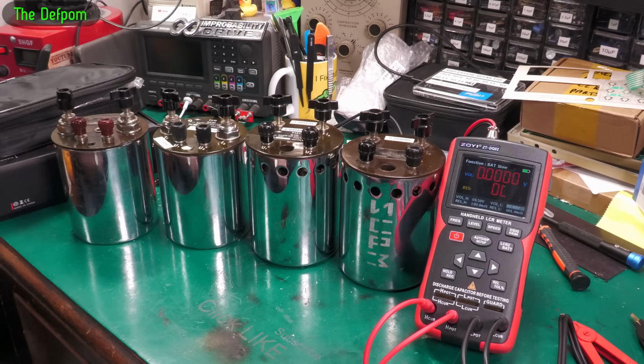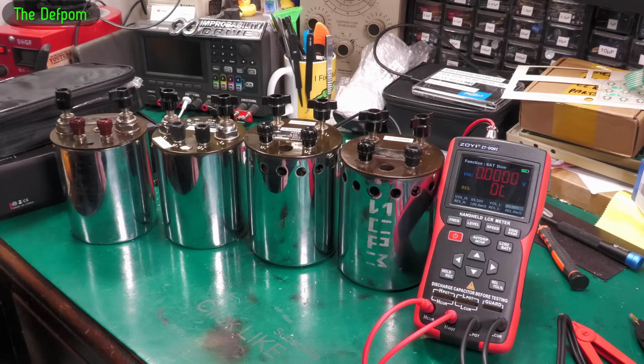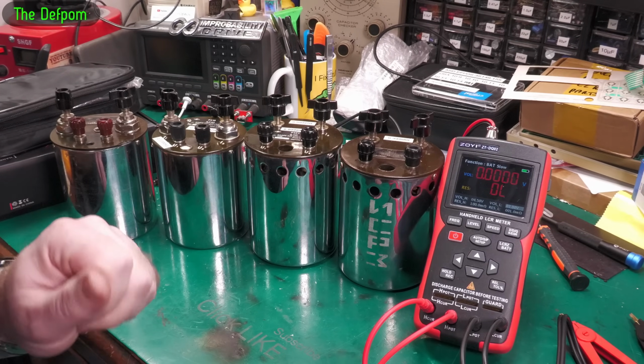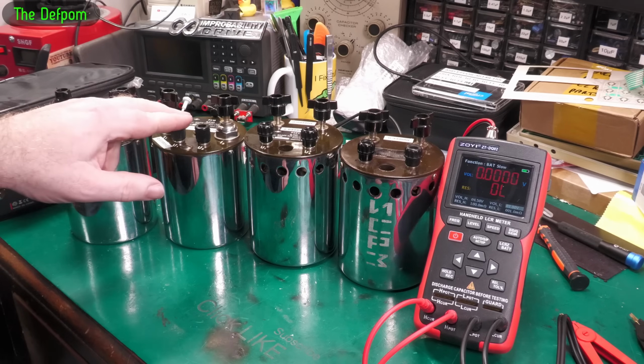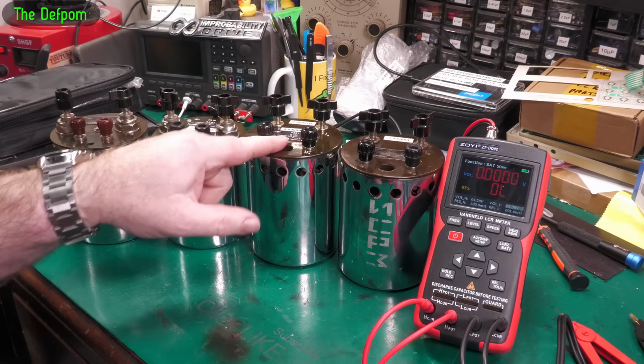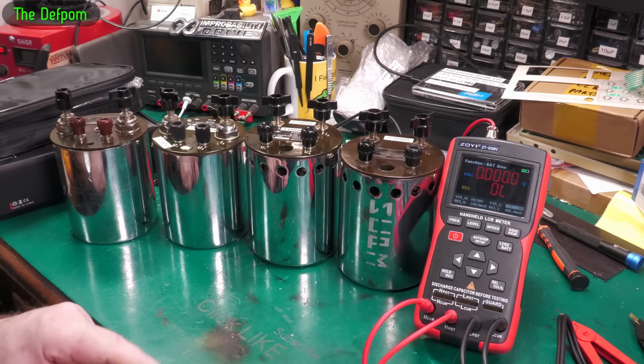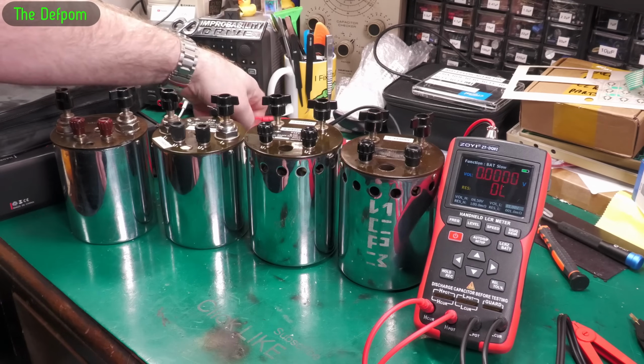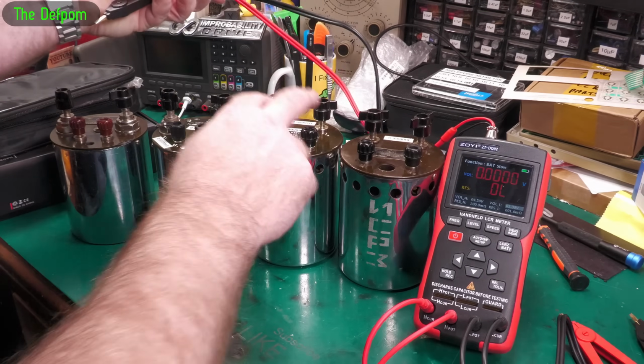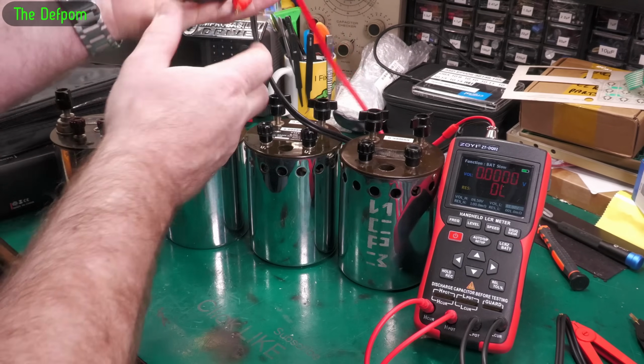So here's the first batch of resistors. I've got loads of these things, a range of values: 1 milliohm, 10 milliohms, 100 milliohms, and 1 ohm right here. I've got the terminals prepared. If you're doing this properly, you do a full four-wire measurement, with individual leads going into each terminal. I'm just going to use the clip leads because it's going to be good enough for this example.